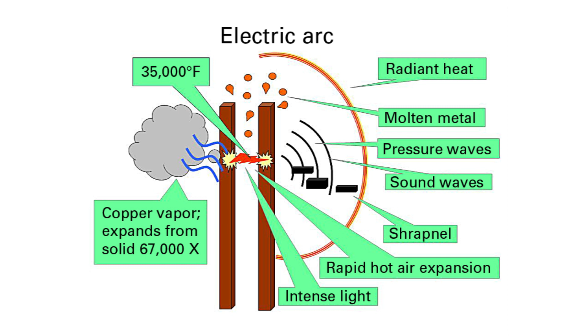The unique aspect of an arcing fault is that the current flows through air as opposed to through conductors. The product of fault current and arc voltage concentrated at one point results in tremendous explosive energy. High temperatures cause copper to rapidly expand and vaporize, causing extreme thermal energy. Molten metal is blown out, which can cause severe burns and ignite flammable clothing. Blast pressure from the vaporization of metal and superheating air is high enough to rupture eardrums, fracture ribs, and collapse lungs. An arc flash event is very serious.